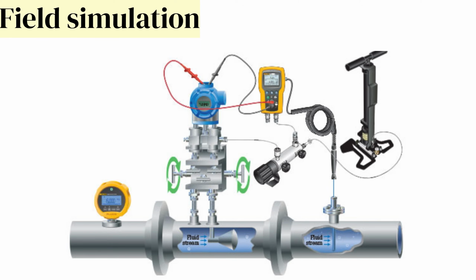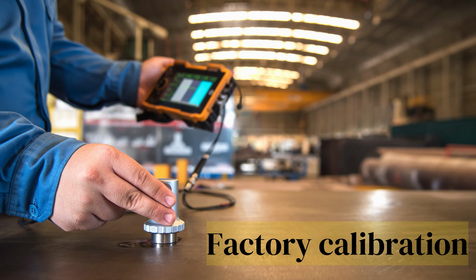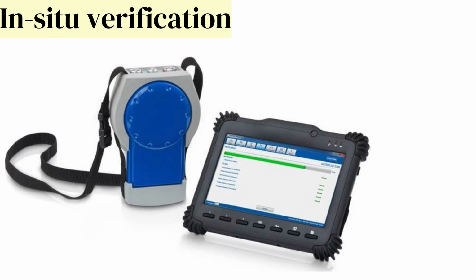2. Factory calibration. Before installation, flow meters can be dry calibrated at the factory using precision calibration equipment that simulates various flow conditions. In situ verification. In situ verification is a non-intrusive method that checks the flow meter's performance while it is installed and operating in the process line. This method typically involves software and diagnostic tools provided by the flow meter manufacturer.